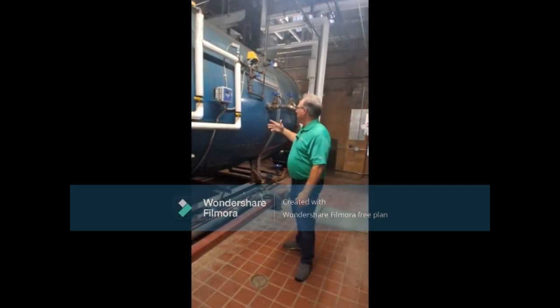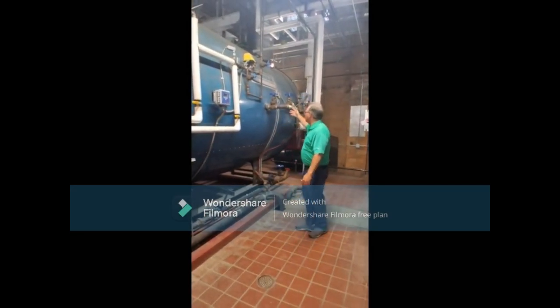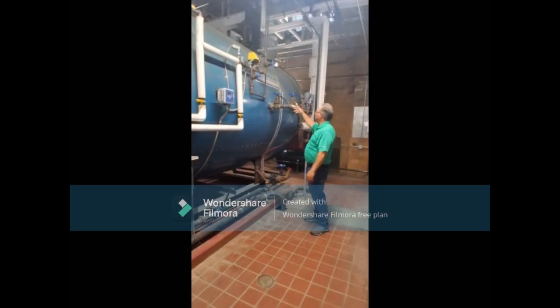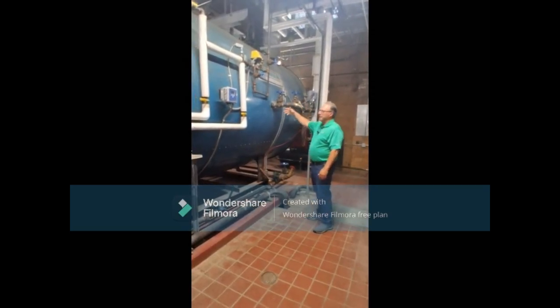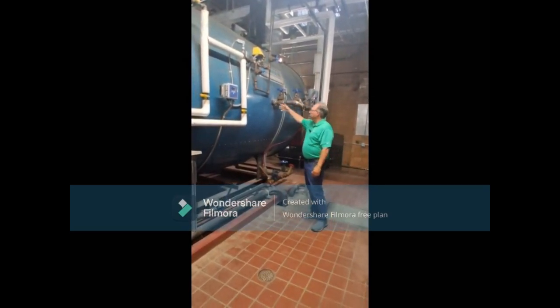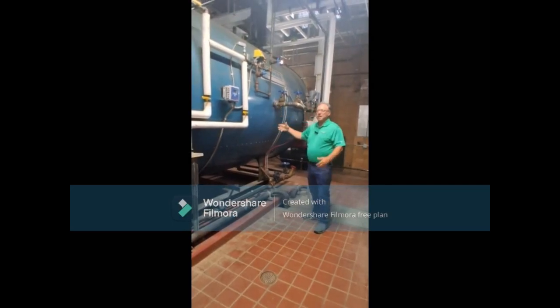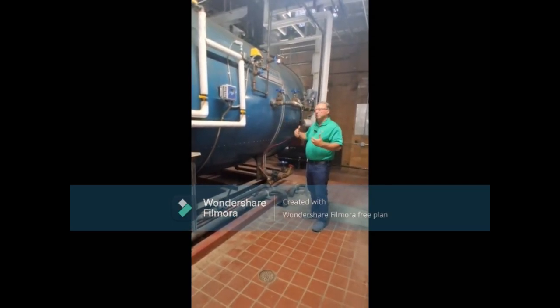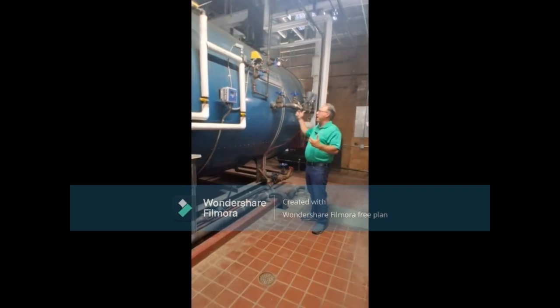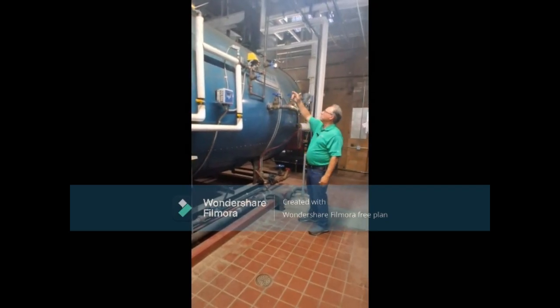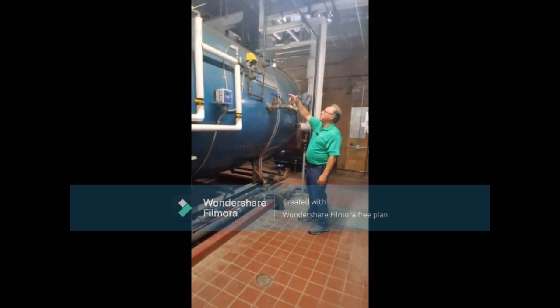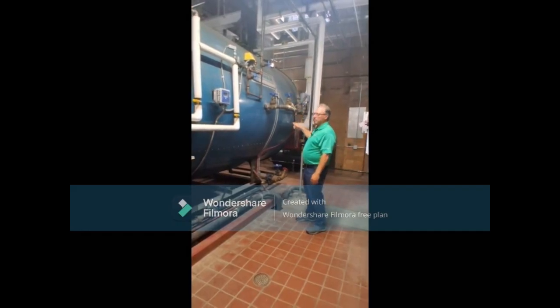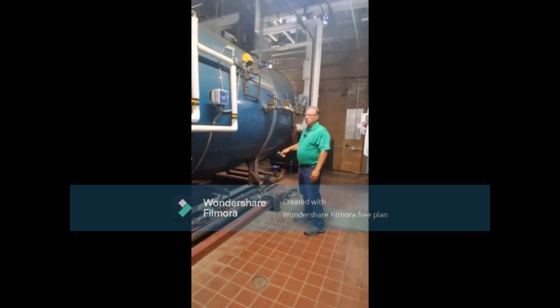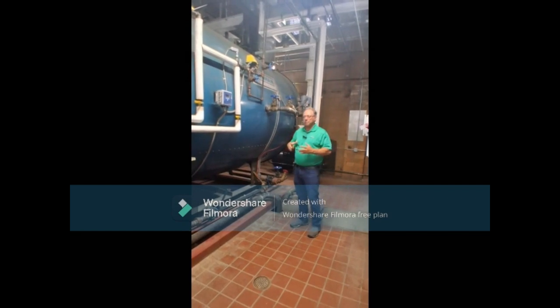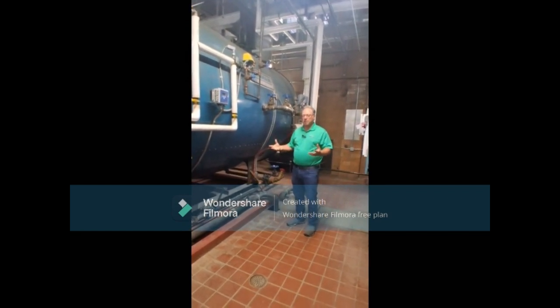So when we have our probe system in here, as you see here, we're able to valve off, take this probe out and clean it, put it back in, and this probe system will see the water in the boiler itself, to bring all the energy out, take it to the control system, come back, and then we attach it to different parts of the tower or different parts of the boiler on top, and we go to an independent ground rod. So each boiler will become the same polarity as the water inside, so you don't have a negative-positive reaction.